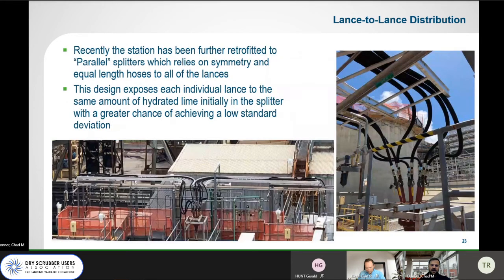So that led to the most recent upgrade, where we transitioned to what we use on all of our new systems, what I call parallel splitting, where all the hydrated lime comes into one splitter, and this splitter design relies on symmetry and equal length hoses and pressure drop to equally distribute all of the lime. So basically this splitter exposes all of your lances to the same amount of hydrated lime in one compact spot. So they all have a greater chance of achieving a low standard deviation of hydrated lime being delivered to each individual lance.